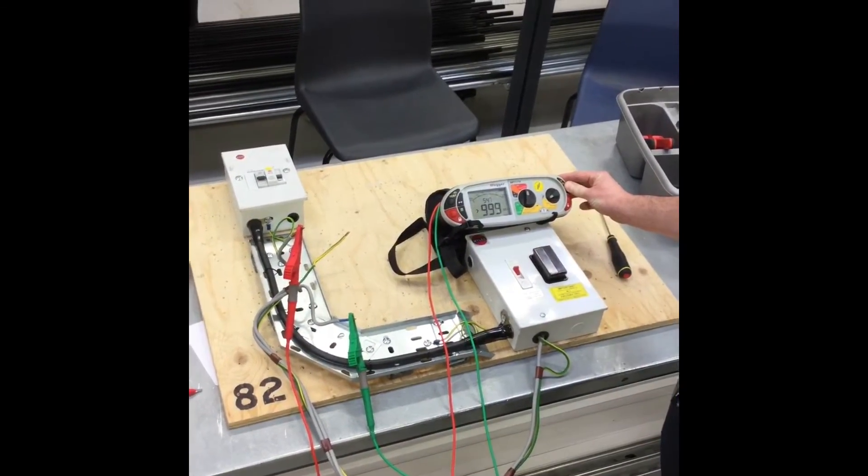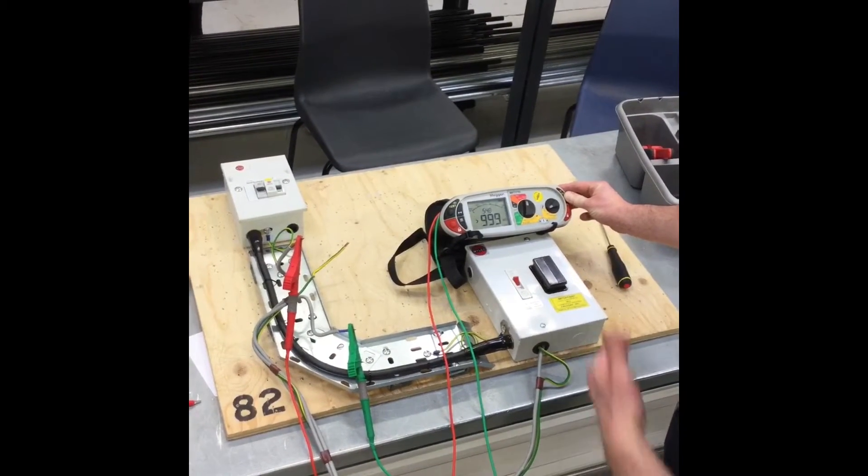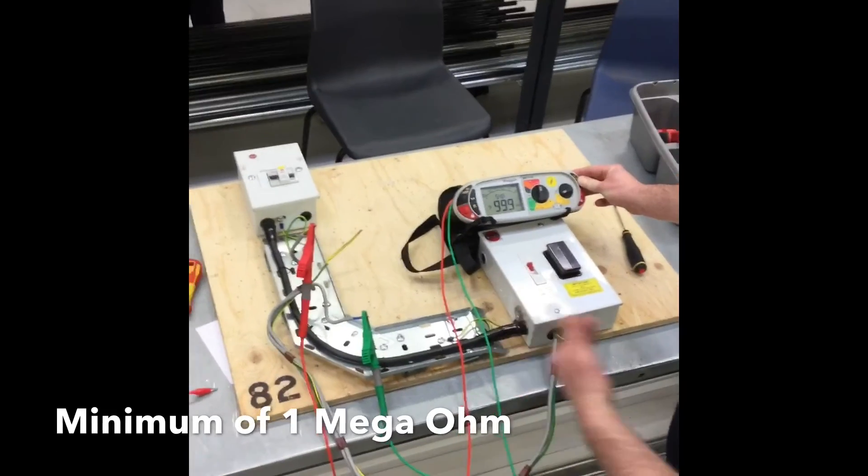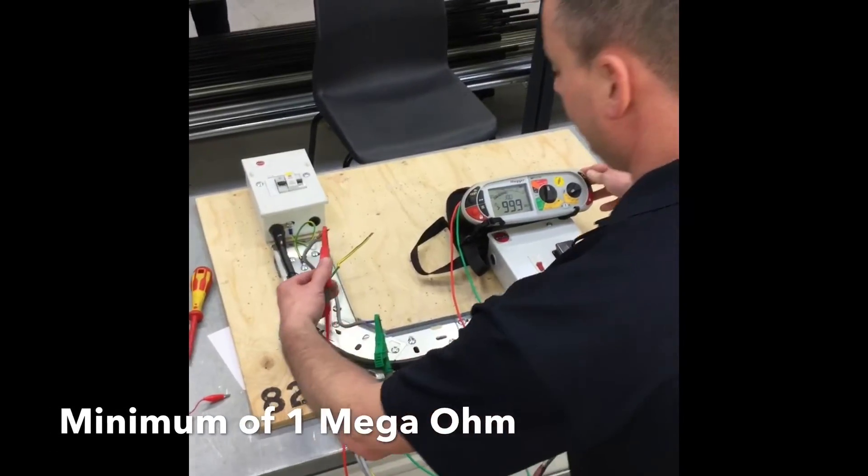Insulation resistance is greater than the machine can read—greater than 999—above the minimum accepted of one mega ohm, below two mega ohms where further investigation is required. Move around.